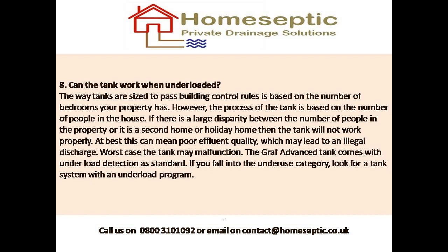Say it's like your country retreat and you're living in London for half the time, then the tank's designed for nine persons, and a normal tank will just work to that limit. And if there isn't the effluent coming in, it just doesn't really work properly. It can affect your effluent quality. It can make the tank break effectively. So the Graf Advanced has an automatic sensor to work to the load. So it's a really good option for anyone who has to have a big tank because of the size of the bedrooms, but doesn't use it to its full capabilities.